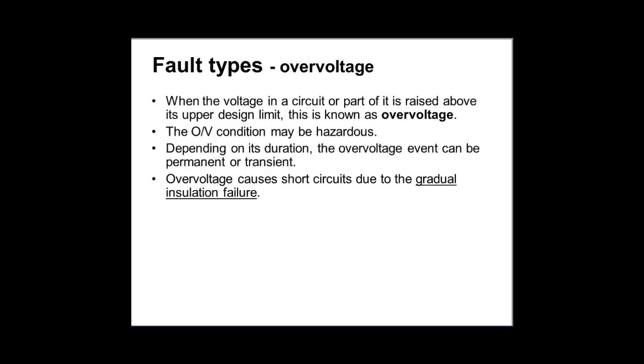under frequency relays, so that as soon as the expected current goes above the rating, the relay will operate and will trip the circuit breaker that is connected to that. If the voltage of the system goes above the rating, the over voltage relay would operate. If it goes below the rating, the under voltage relay will operate. If the frequency goes above the 50 Hertz, the over frequency relay will operate. If it goes below the 50 Hertz, the under frequency relay will operate.